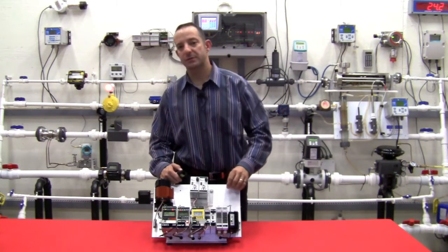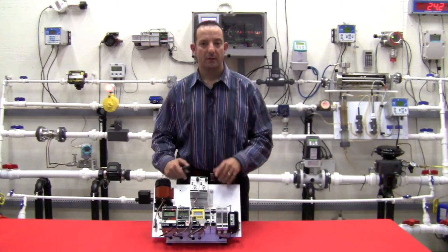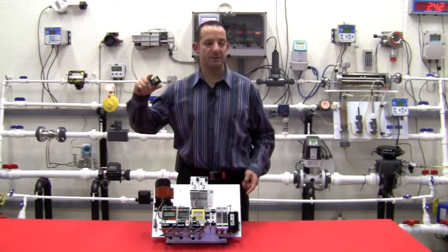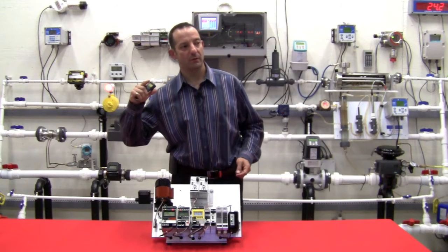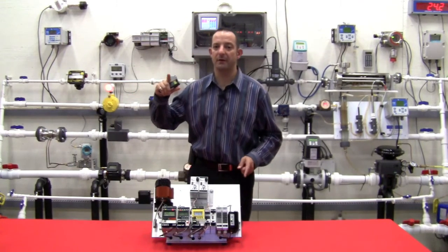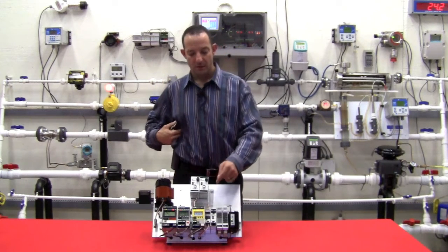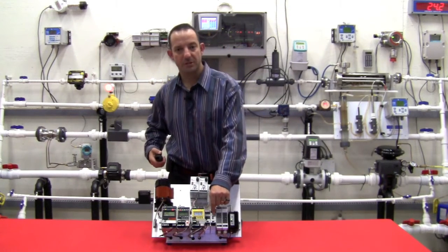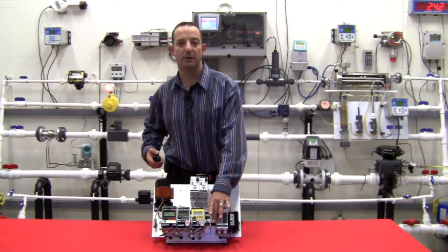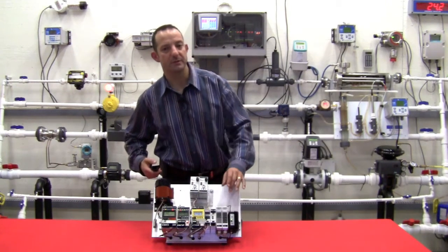But using that control system input card, that 18-bit resolution is spread out over the entire range of that J-type thermocouple input, which is something like 0 to 1200 degrees Fahrenheit. So you can see right off the bat, we achieve a 4-to-1 improvement in resolution of that temperature measurement by using the transmitter.